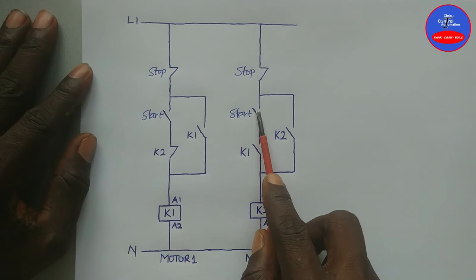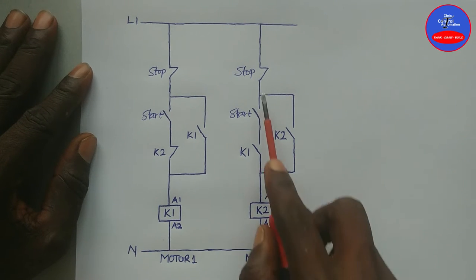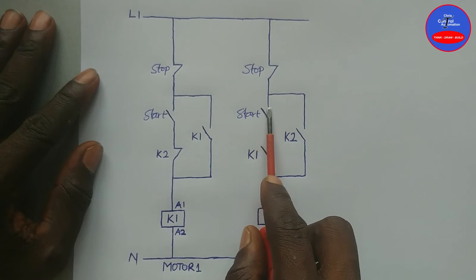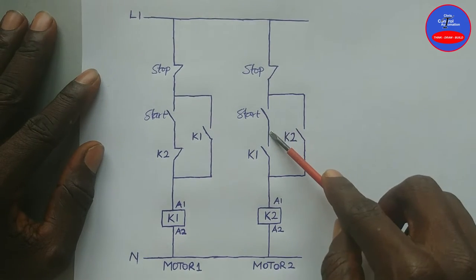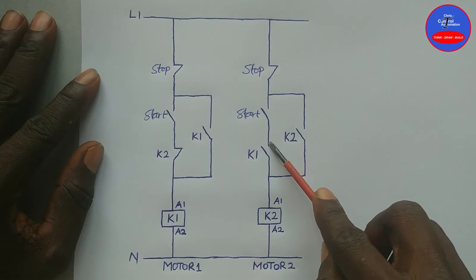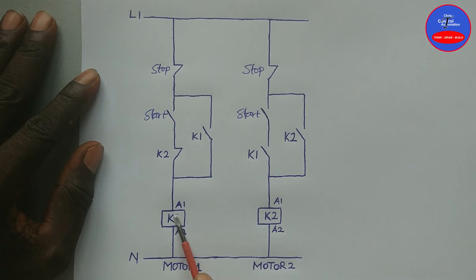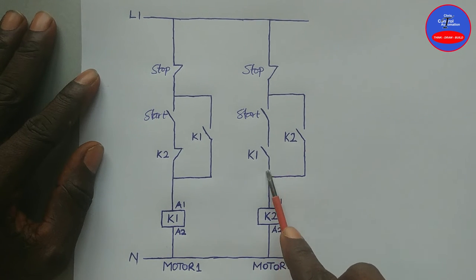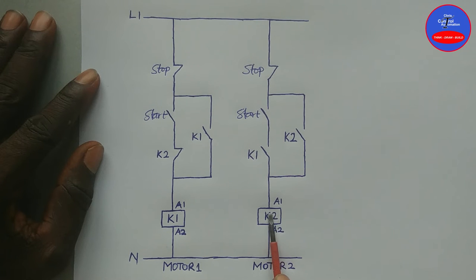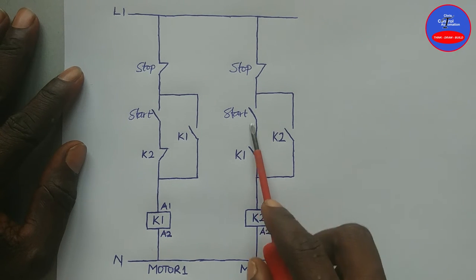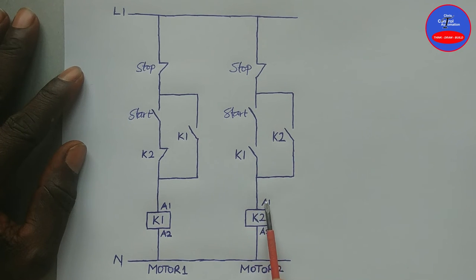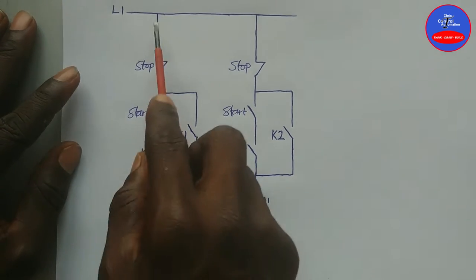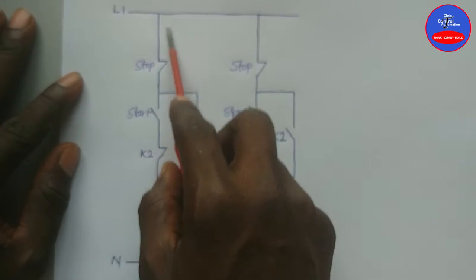In case you want to start Motor 2 first, let's see what happens when you press on the start button. Current will flow through to this point, but when it gets here, because K1 is not energized, there is no way the current can continue to flow through to energize K2 or Contactor 2. This is the main reason why Motor 2 can never be started until Motor 1 is running.